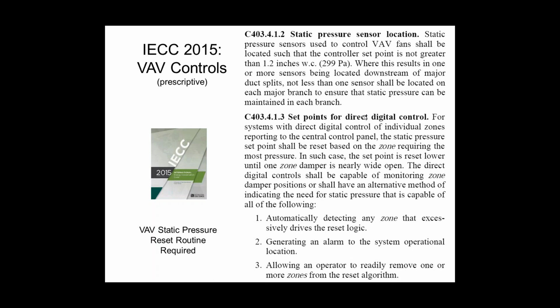automatically reset. So yes, I'm controlling the 1.2 inches of static in the duct there, but I have to be able to reduce that as zones don't need air. We call this static pressure reset. A common routine would be if I look at all my VAV boxes, and by I mean the computer, if the computer looks at all the VAV boxes and nobody's open more than say 80%, obviously I'm providing you too much air because nobody wants all of the air, everybody's throttling back. Therefore, I should reduce your static pressure set point from 1.2 inches down to 1.1 or whatever it was. And I'll keep reducing that until somebody's open like 95% or something like that. Then I'll stop doing that, right? And then if somebody gets closer to 100% open, I'll say, oh, they must want more air, and I'll start bumping the set point back up. You have to do this automatically. Automatically means without human intervention, right?